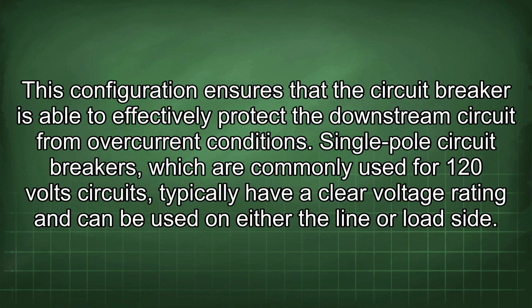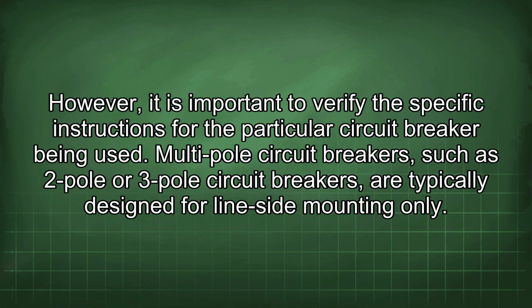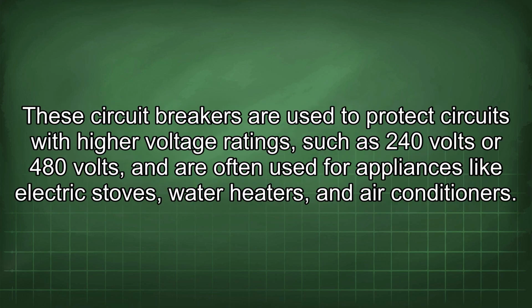Single-pole circuit breakers, which are commonly used for 120-volt circuits, typically have a clear voltage rating and can be used on either the line or load side. However, it is important to verify the specific instructions for the particular circuit breaker being used. Multi-pole circuit breakers, such as 2-pole or 3-pole circuit breakers, are typically designed for line-side mounting only. These circuit breakers are used to protect circuits with higher voltage ratings, such as 240 volts or 480 volts, and are often used for appliances like electric stoves, water heaters, and air conditioners.